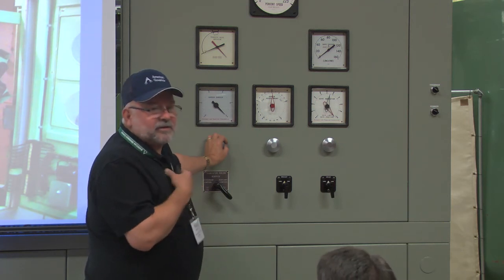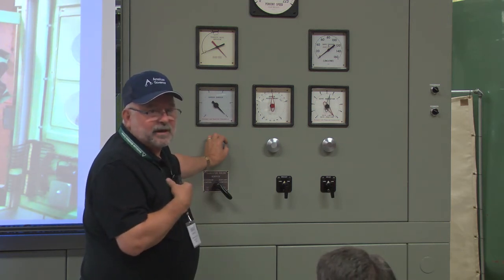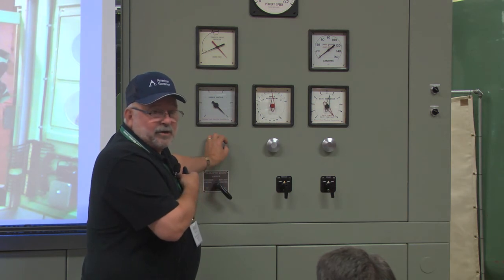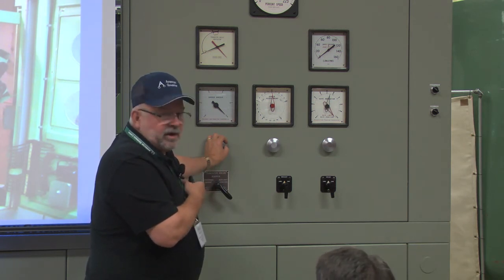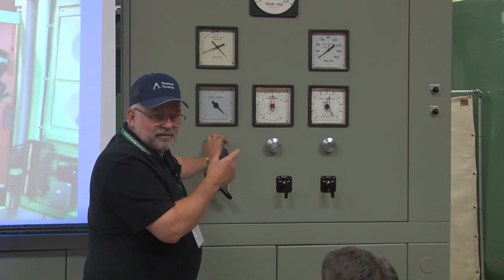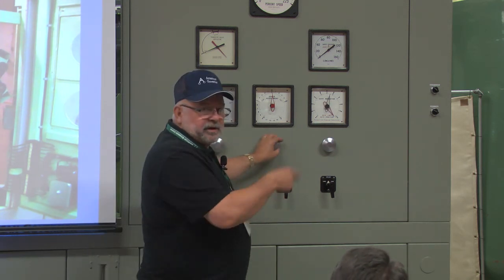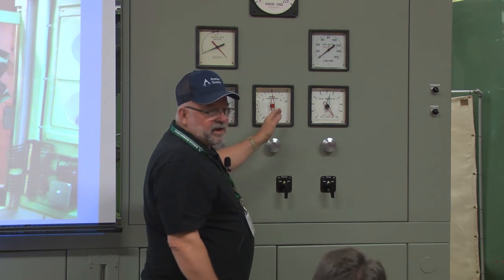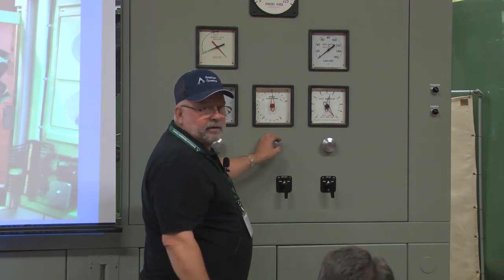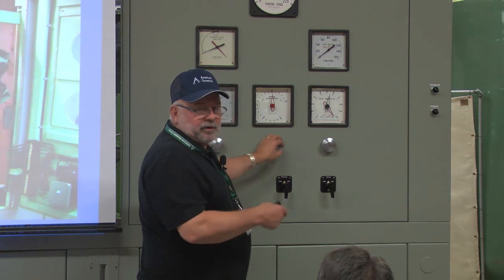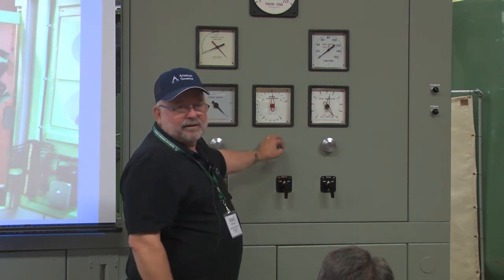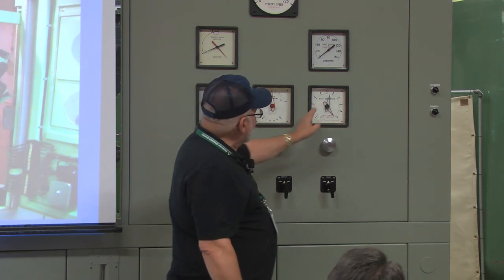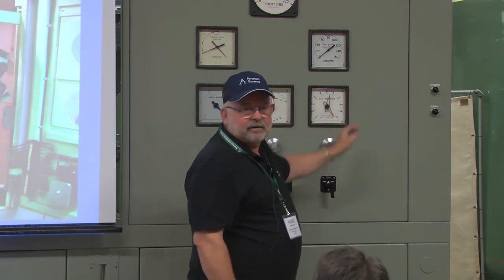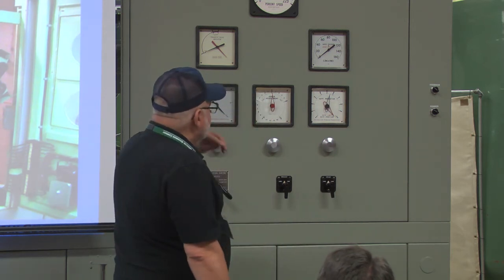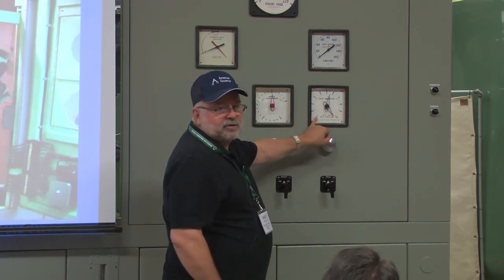So that tells me, that's the true calibration of droop for me, rather than calibrate it in the dry, I just watch it go online, make sure that I've got the response. When the guy starts the unit up and he's up there and he's parallel and he's got about a megawatt on it, I said, hey, you mind if I just go down there? And I gave one turn on it and make sure it goes from 18 to 22% gate. Then I know. Sometimes he lets me do it on both sides so I can see if it's balanced, because there'll be a little difference one side or the other. When you guys close your gates, do you set it at 0?